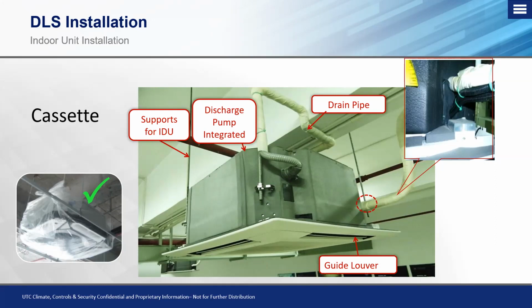The nice part about these units is that on the bottom side there are two clips that open up, and the beauty plate will drop down. You can access your fan motor, your condensate lift mechanism, and also your electrical section to do all your service work, aside from the drain pump line and the refrigeration line sets, all from within the space that the cassette is serving.